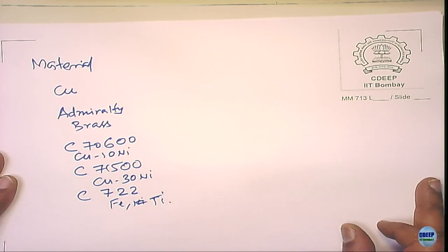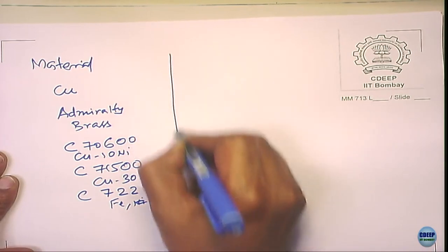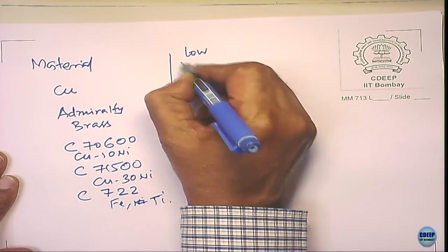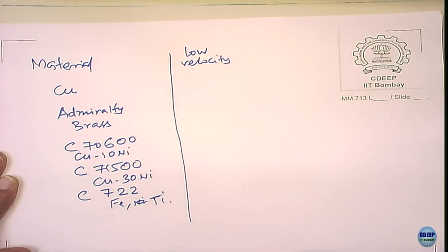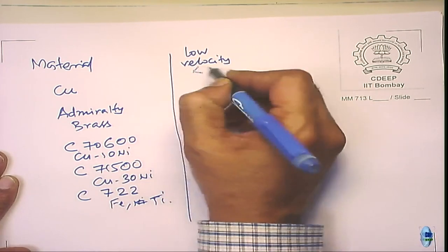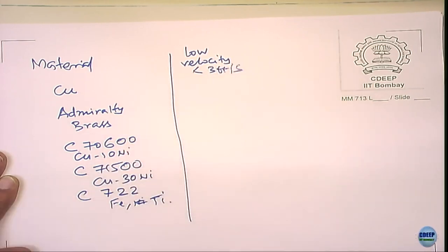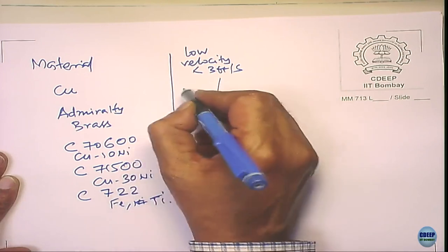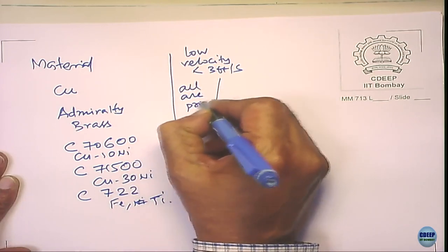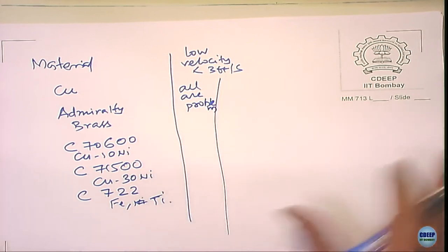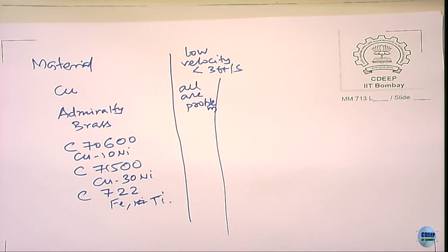If you look at copper, in fact it is very interesting. Low velocity, if it is going to be less than 3 feet per second, all are problem. You know why? You take a pipeline, you take a heat exchanger, when the flow velocity is low, they are not the right material to use. Any idea about it? What do you think? Low velocity is also a problem.